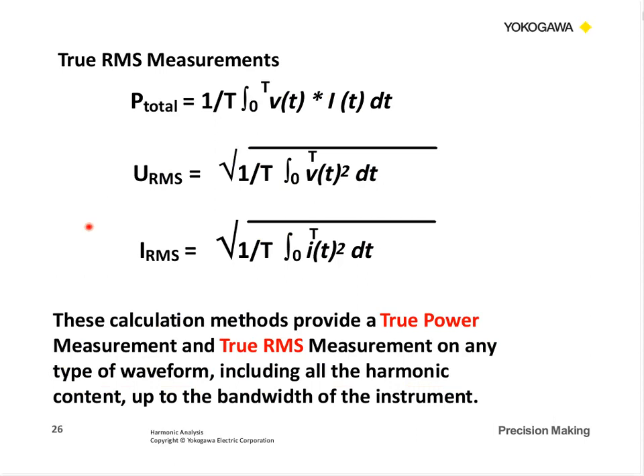Now these calculations provide a true power measurement and a true RMS measurement, and it is done on any type of waveform. It includes all the harmonic content up to the bandwidth of the instrument. So when we get a distorted waveform, these algorithms will give us the true power and the true RMS measurement, regardless of what we have, but it is up to the bandwidth of the instrument.